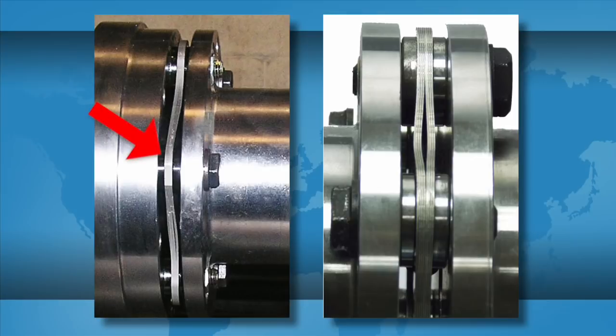If there is any waviness in the disc packs, the equipment alignment will need to be corrected prior to continuing. If there is any bowing or separation of the disc layers, loosen the bolts on each side of the bowed area. Reapply a thin film of grease or lubricant under the surface of the lock nuts and re-tighten.